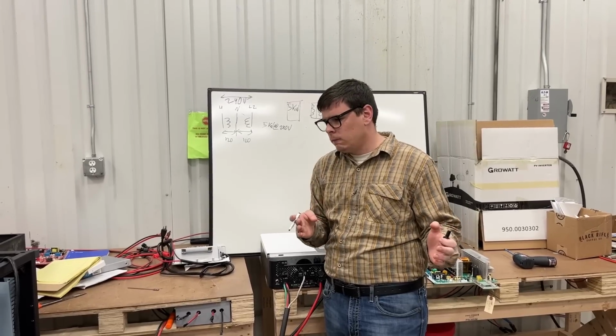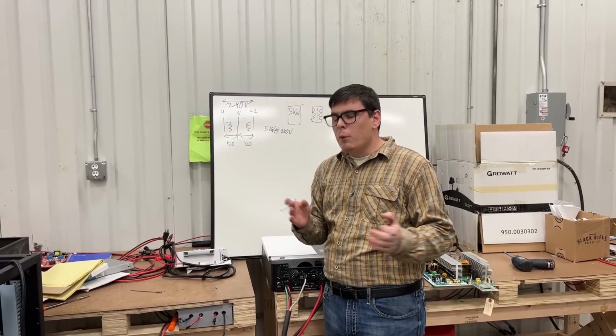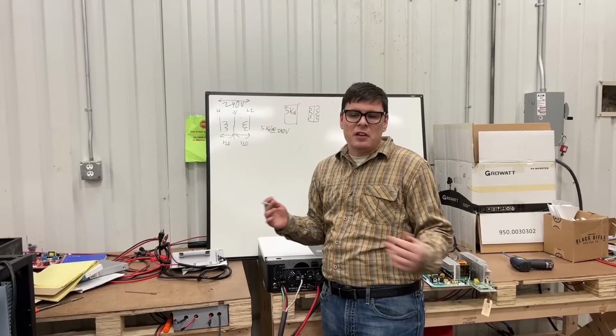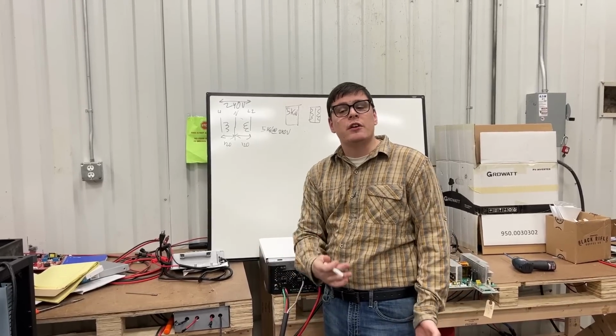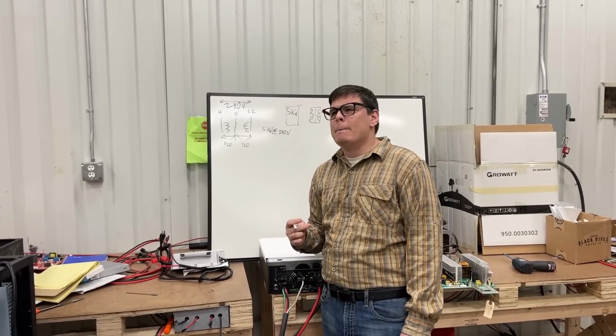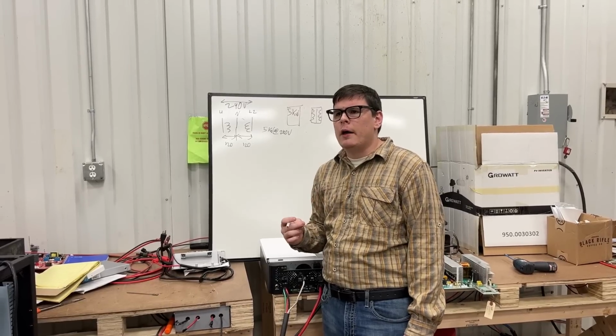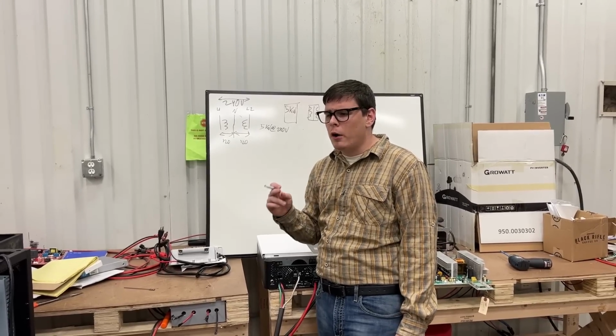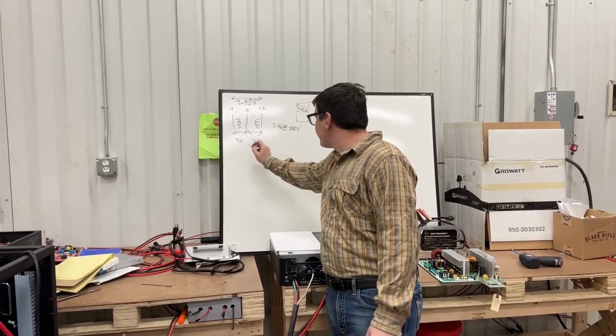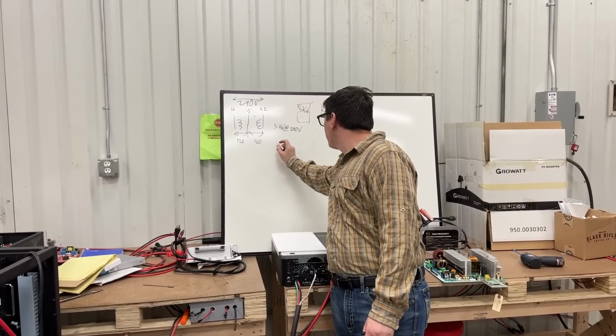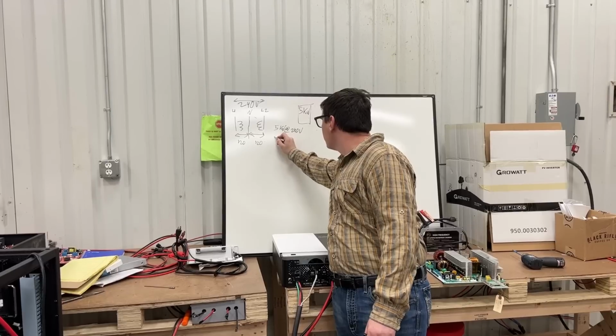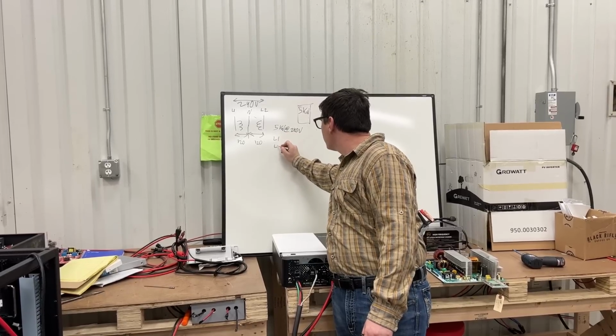If you do that, then you'll be 5 kilowatts imbalanced, and that's technically a little more than one transformer can handle. You should get a second transformer. But if you got 5 kilowatts, the thing about autotransformers is that if we write this out in terms of line 1 and line 2.